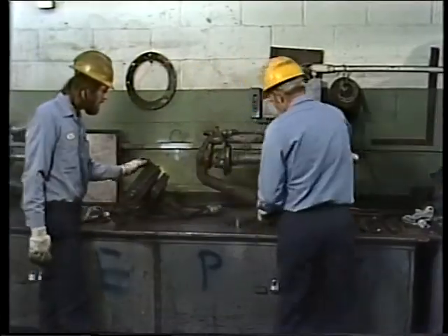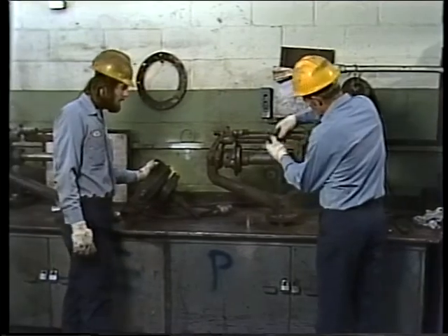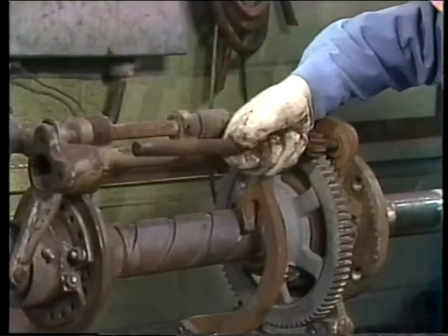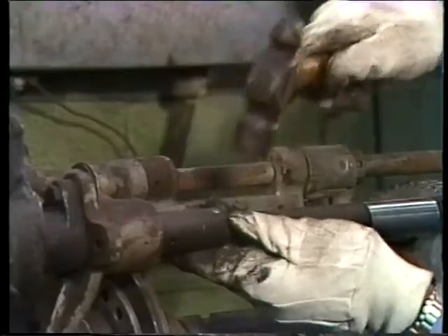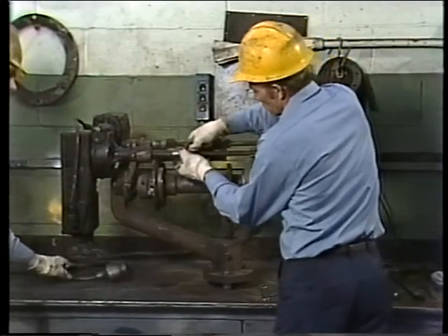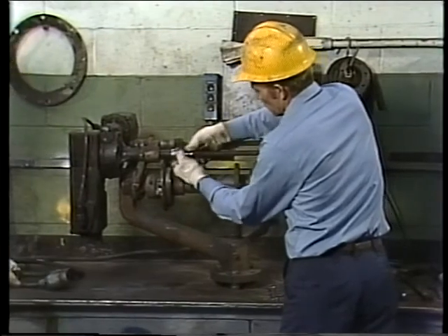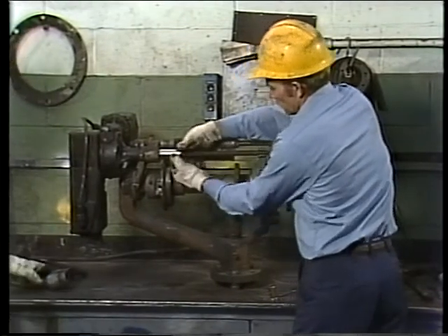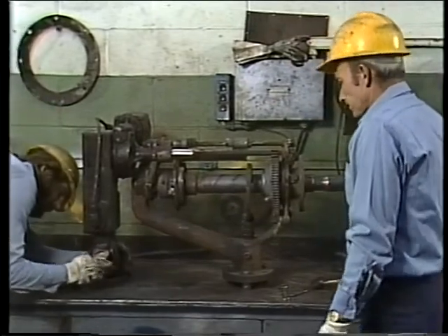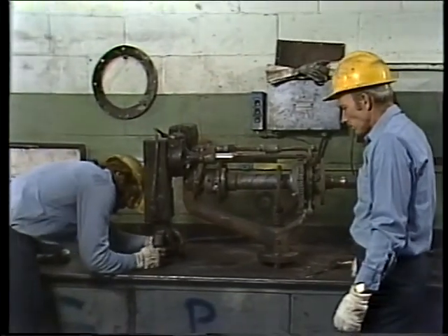The last step in reassembly on the bench is the reinstallation of the motor drive. The drive shaft and gear slip into place, and the motor drive output goes over the other end. A scroll pin that connects the 2 is hammered into place, and a metal collar fits over the assembly to safely retain the scroll pin. After the motor drive mechanism is in place, the power connection can be made, and the soot blower can be bench tested under power.